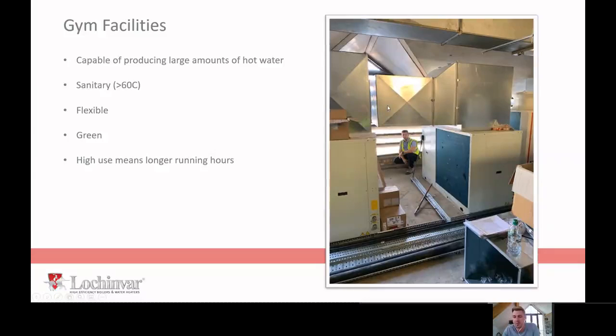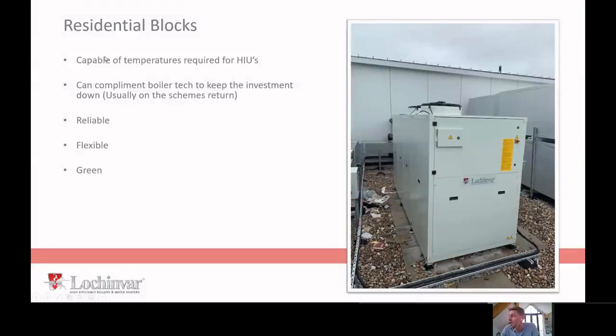Duct to the fanned outlet, put the unit inside. You can have air source heat pumps in an indoor environment if you've not got a suitable roof to mount them on. And what this does is, any plant room I've ever been in, it's the hottest room in a building. So this creates and simulates an environment where the air source heat pump is picking up warm air. If it's -4 outside, I guarantee it's not -4 in your plant room. This heat pump's going to work effectively all year round. But yeah, gyms and leisure facilities, definitely a good place for them.